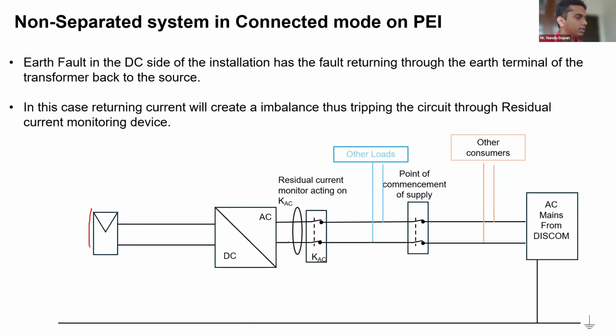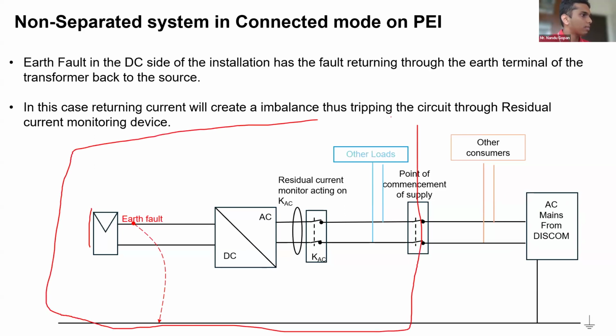Earth system referencing conductor has not been done in this PV. Only in the discom it has been done. So basically, you can consider this as a TT source. The system referencing is done only in the discom. And if there is a fault in the PV, that means in the connected mode, the grid, the discom, is also connected to the PEI. PEI starts from here. This is PEI.